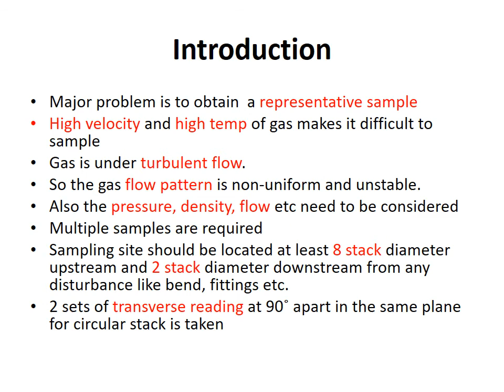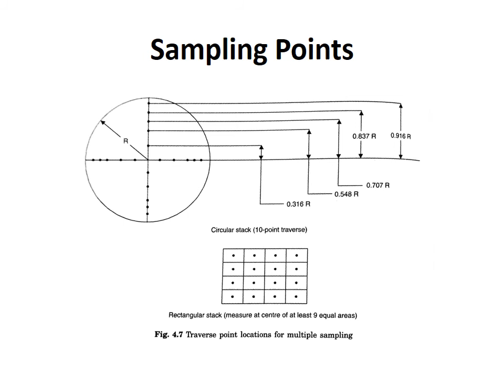Multiple samples are required and the sampling site should be located at least 8 stack diameter upstream and 2 stack diameter downstream from any disturbance like a bend, fitting, etc. 2 sets of transverse readings at 90 degrees apart in the same plane for a circular stack are taken. As you can see from the figure, for a circular stack, the dots represent the various sampling points. So they are taken across the two diameters spaced away from each other. In the case of a rectangular stack, the sampling points are as shown in the figure.